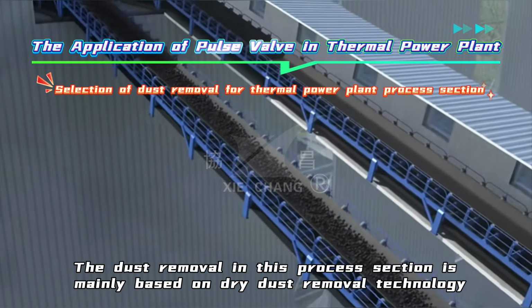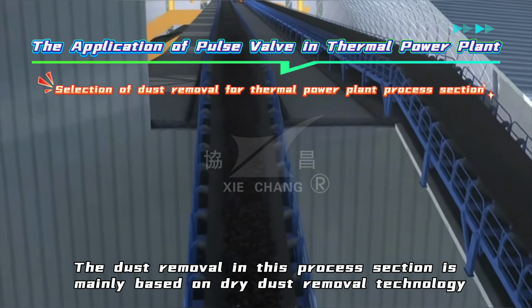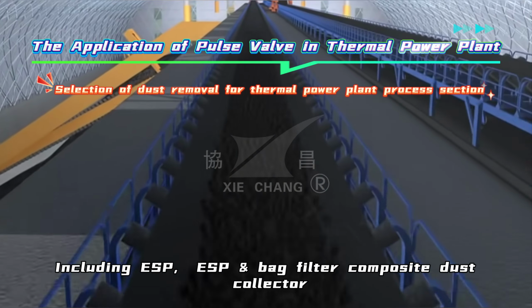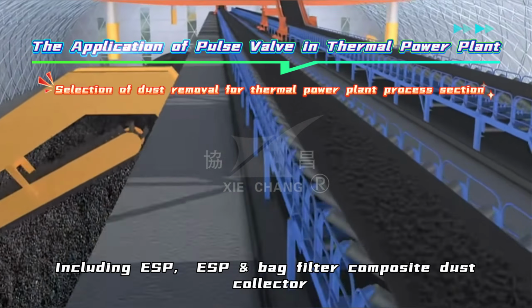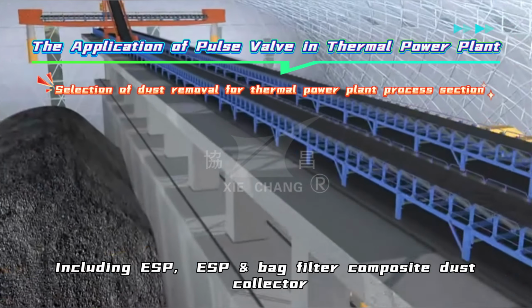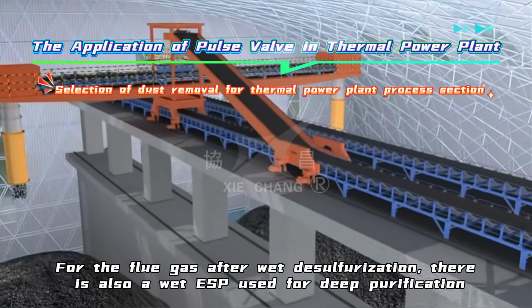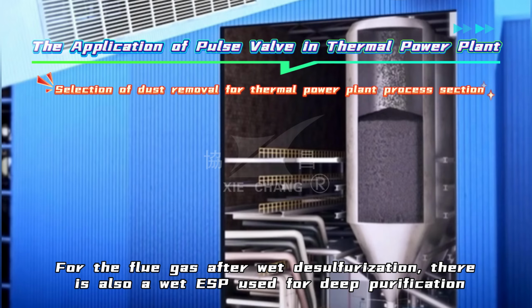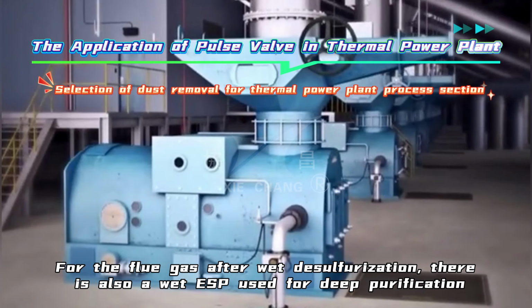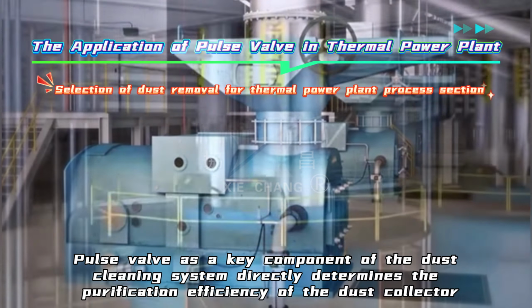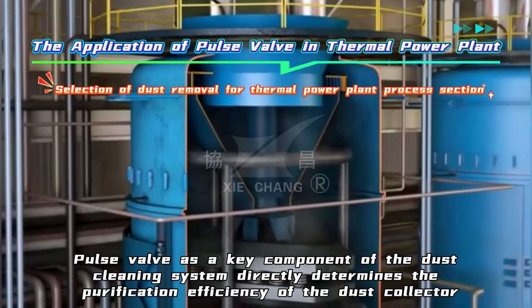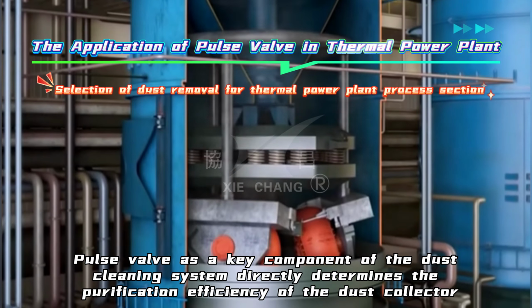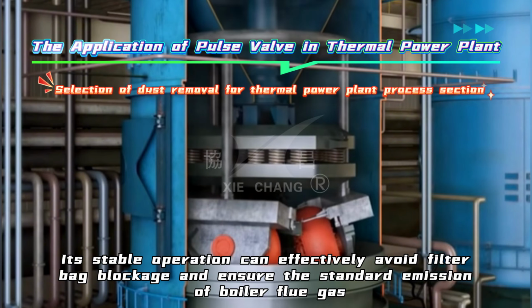The dust removal in this process section is mainly based on dry dust removal technology, including ESP, and bag filter composite dust collector. For the flue gas after wet desulfurization, there is also a wet ESP used for deep purification. Pulse valve as a key component of the dust cleaning system directly determines the purification efficiency of the dust collector. Its stable operation can effectively avoid filter bag blockage and ensure the standard emission of boiler flue gas.